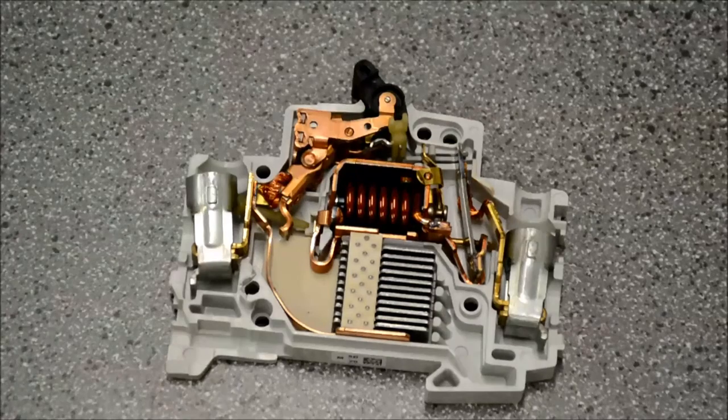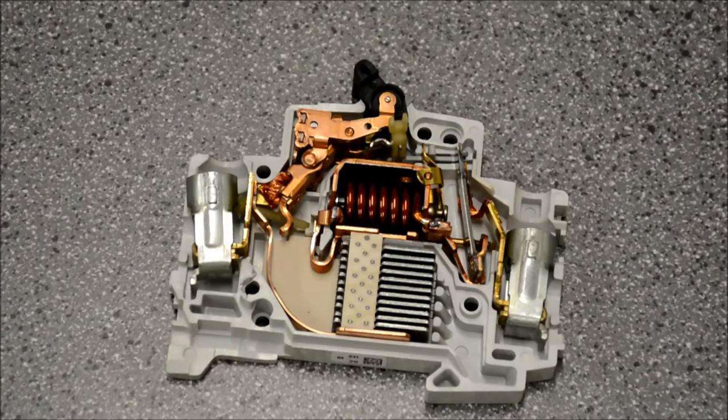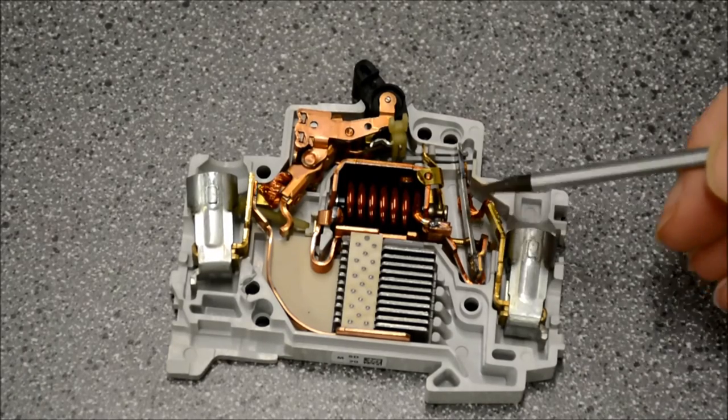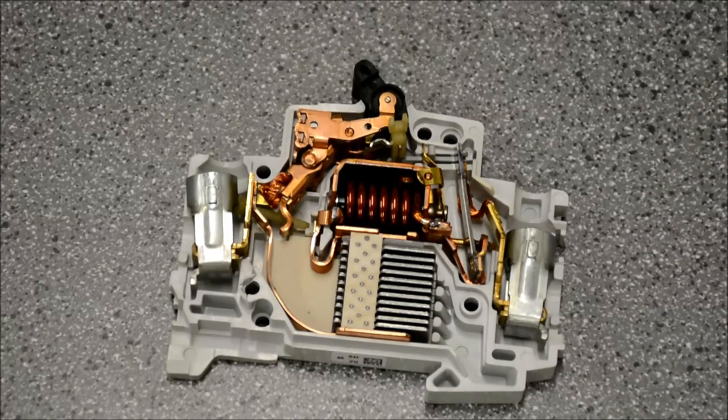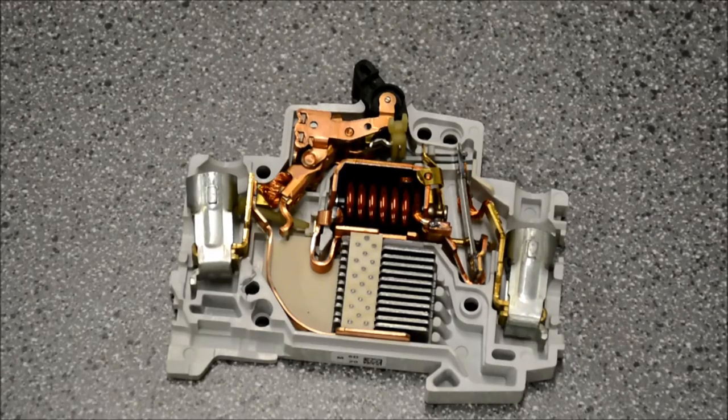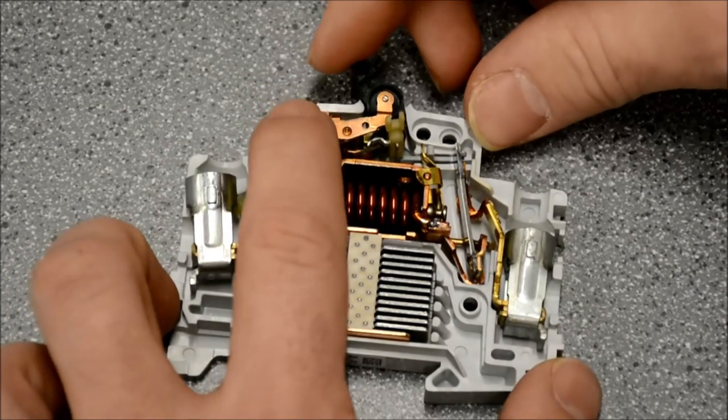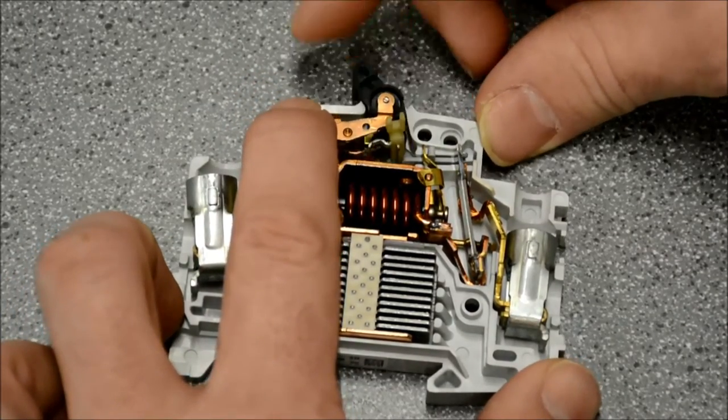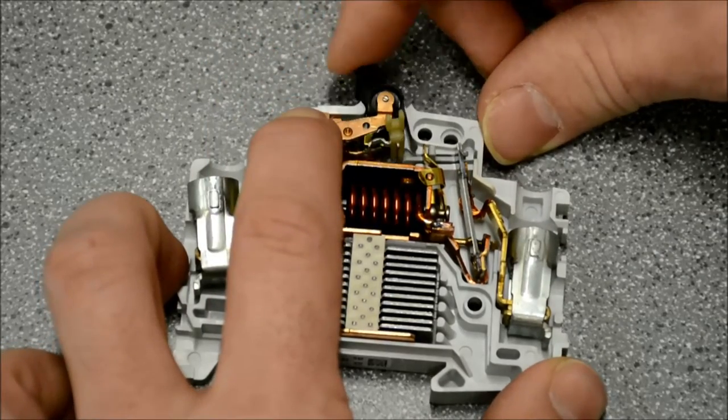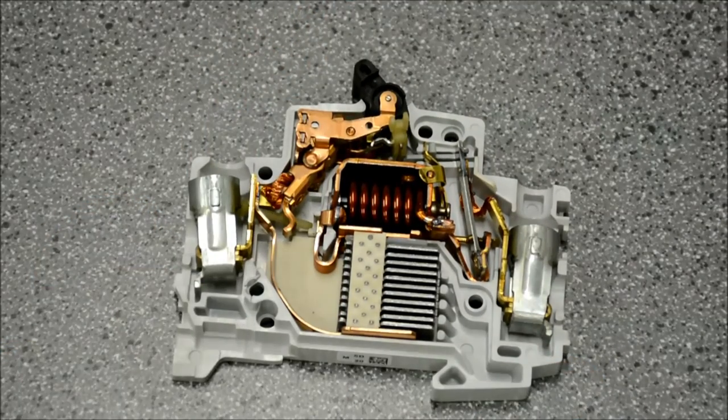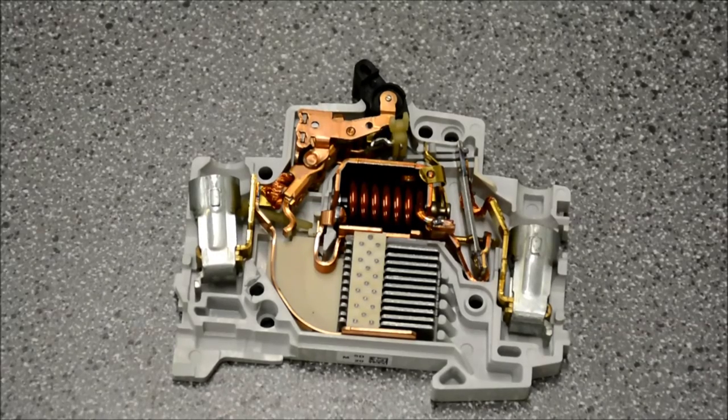What you should notice now that we've heated the bimetallic element is it still shows some curvature, because it's not cooled down to ambient temperature. So if we go inside here and attempt to reset the circuit breaker, we're not going to be able to reset it, because the ambient temperature and the bimetallic element are not equal.